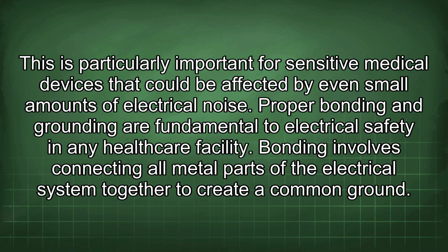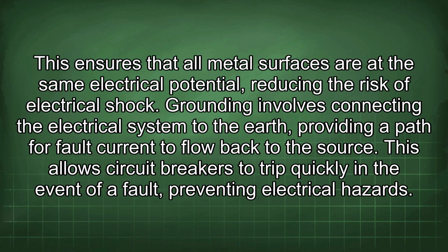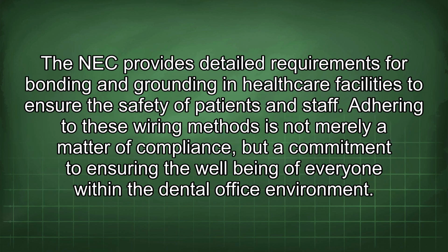Proper bonding and grounding are fundamental to electrical safety in any healthcare facility. Bonding involves connecting all metal parts of the electrical system together to create a common ground. This ensures that all metal surfaces are at the same electrical potential, reducing the risk of electrical shock. Grounding involves connecting the electrical system to the earth, providing a path for fault current to flow back to the source. This allows circuit breakers to trip quickly in the event of a fault, preventing electrical hazards. The NEC provides detailed requirements for bonding and grounding in healthcare facilities to ensure the safety of patients and staff.